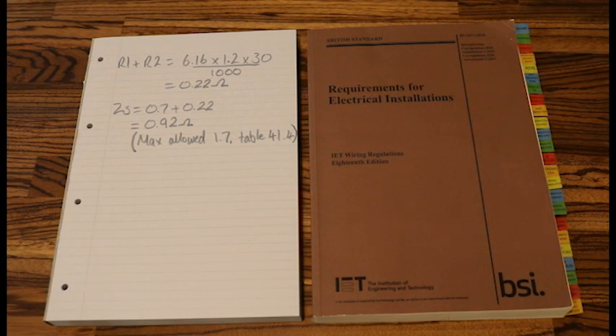So we will skip all of the cable calculation until we get to this point here. I've just calculated my ZS of 0.92, and my maximum value is 1.7, so I can now move on. The next step in the cable calculation, if you've got our cable calculation guide, we are now on step 14.